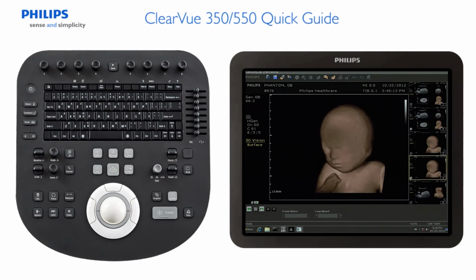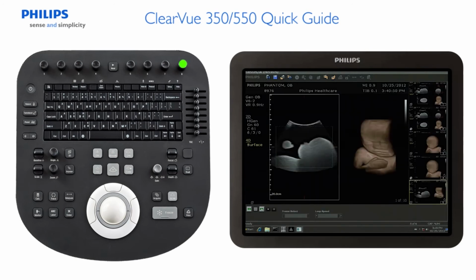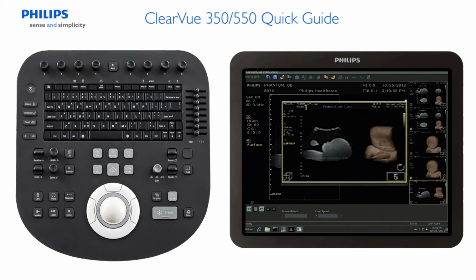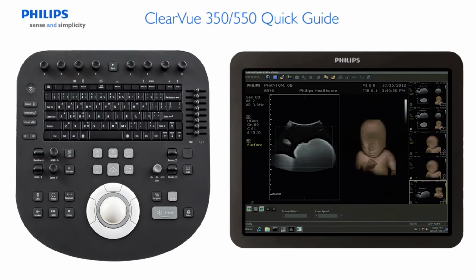To acquire a 4D STIC loop, press Replay Quick key, then press Acquire during the volume Cine playback. In Review, the image will have an empty cube icon to indicate that the image does not contain volume data, and a circle with arrow icon to indicate that the image contains motion. To acquire a 4D STIC loop with volume data, press the Replay Quick key, then press the Save 4D Data Quick key in Volume STIC Play mode. In Review, the image will have both a solid white cube icon to indicate that the image contains volume data and a circle with an arrow icon to indicate that the image contains motion.